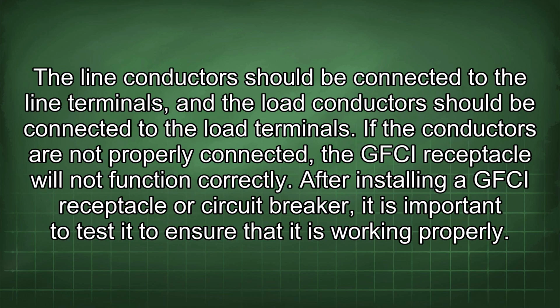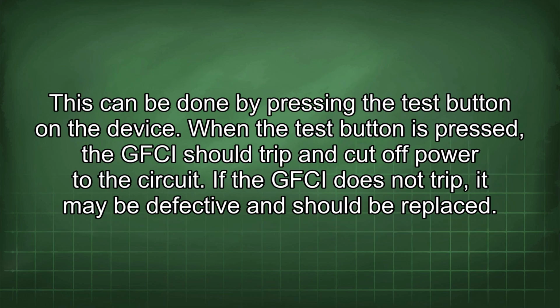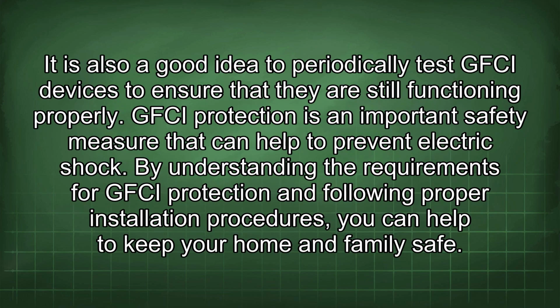The line conductors should be connected to the line terminals, and the load conductors should be connected to the load terminals. If the conductors are not properly connected, the GFCI receptacle will not function correctly. After installing a GFCI receptacle or circuit breaker, it is important to test it to ensure that it is working properly. This can be done by pressing the test button on the device. When the test button is pressed, the GFCI should trip and cut off power to the circuit. If the GFCI does not trip, it may be defective and should be replaced. It is also a good idea to periodically test GFCI devices to ensure that they are still functioning properly.